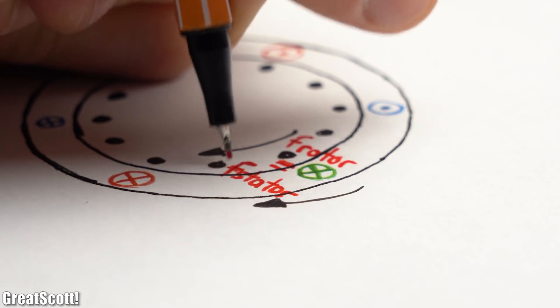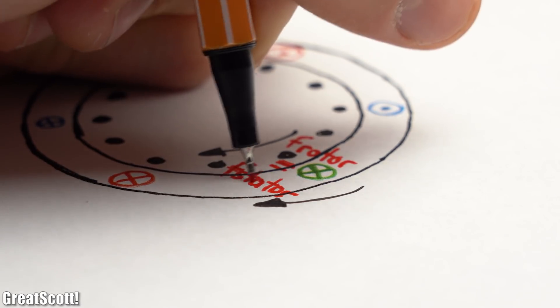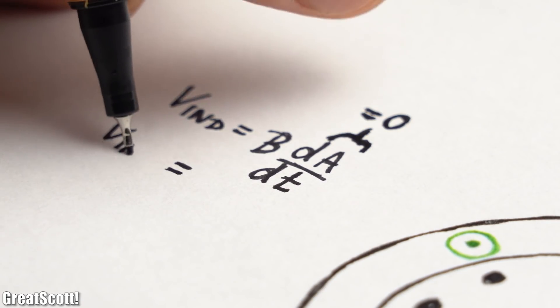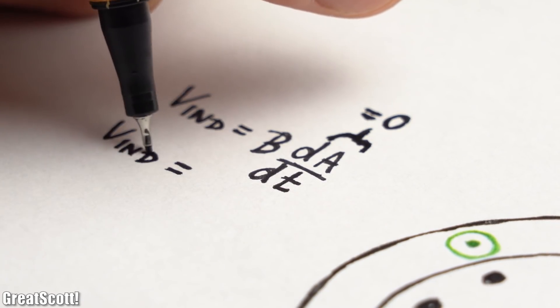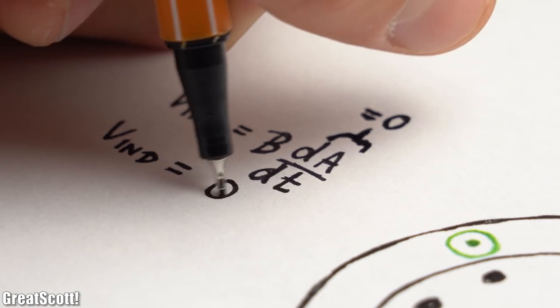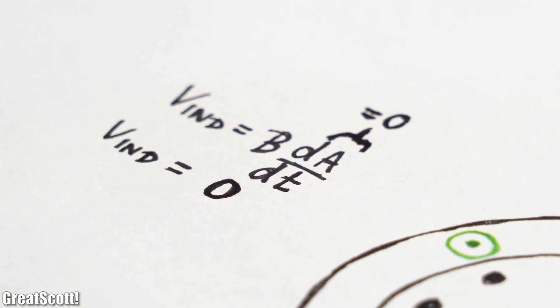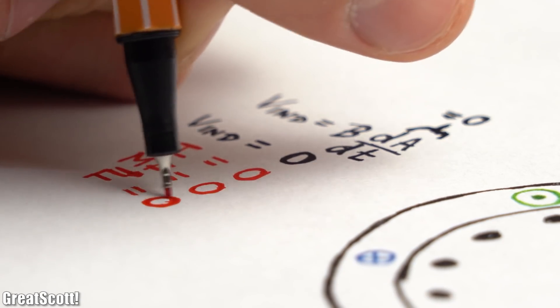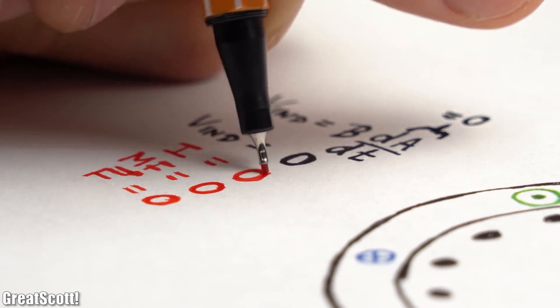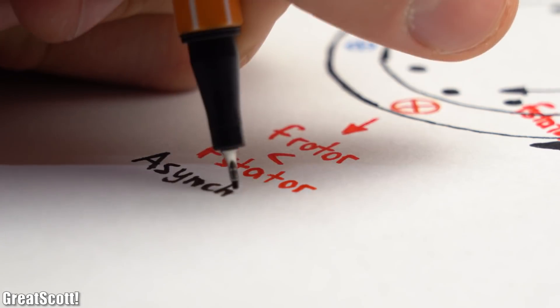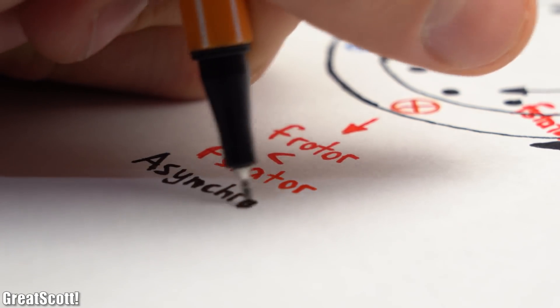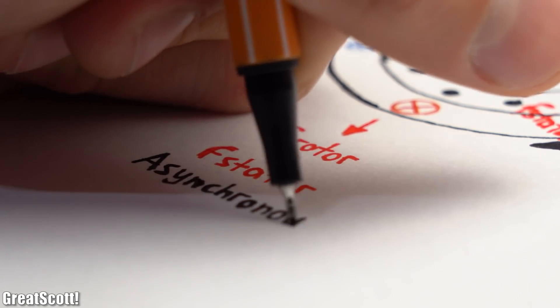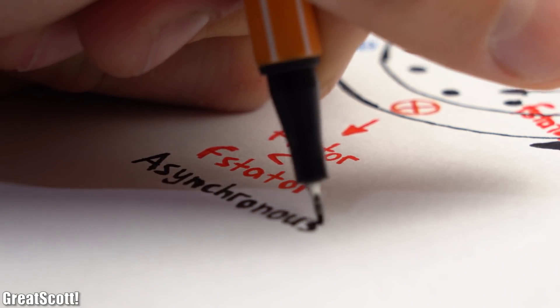Well let's imagine the rotor and stator would spin with the exact same frequency. The problem is that in this case according to the induction law no voltage would be induced into the rotor and thus no current would flow and no opposing forces would be created which means no rotating. So it is pretty logical that the rotor must turn a bit slower than the stator frequency which is also why this motor type is called asynchronous.